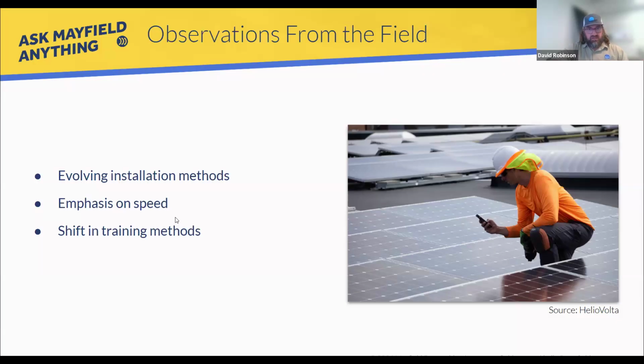Like these older systems that have PID—is that the correct phrase for it? PID—that might now be causing false arc faults. So how do you detect and pick that up? Now we're in situations where we have equipment where we can run a series resistance test. We find it's a connector, a module, or RSD issue. We fix it. But if that inverter manufacturer has a different calibrated scale for the arc fault, it may still trip.